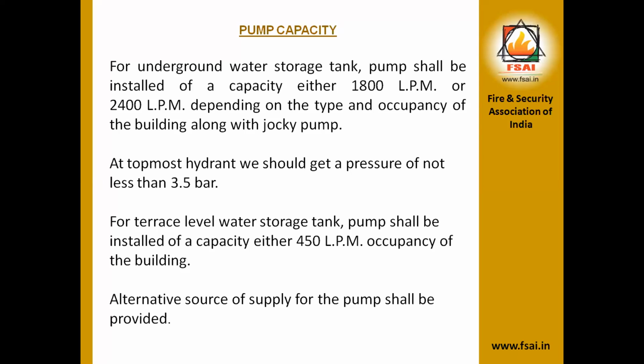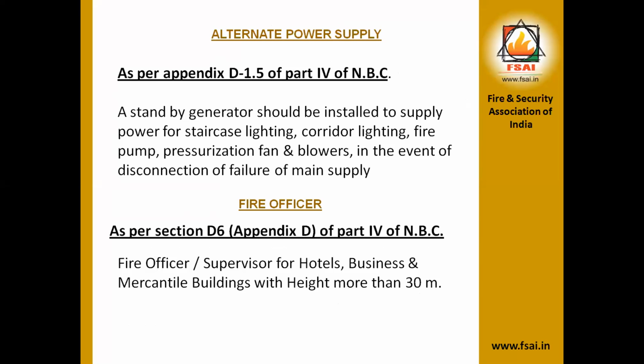For terrace level water storage tank, a pump shall be installed of capacity 450 liters per minute, depending on the occupancy of the building, and an alternative source of supply for the pump shall be provided, so that if one source is not activated, another can serve the purpose. The next is alternative power supply. If the power supply fails, then all systems would collapse. So there should always be an alternative power supply.